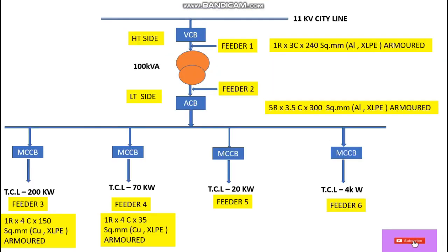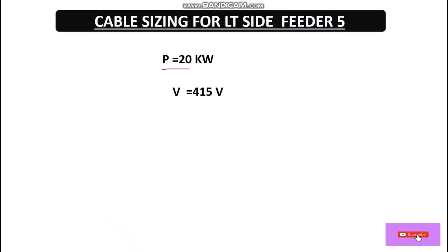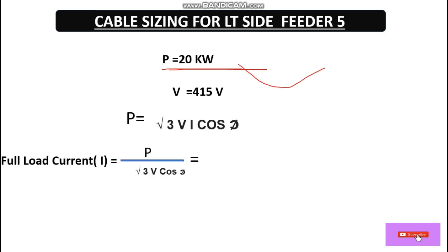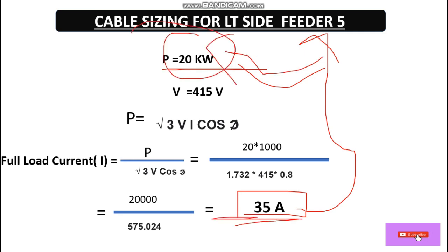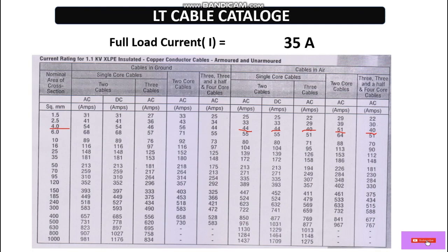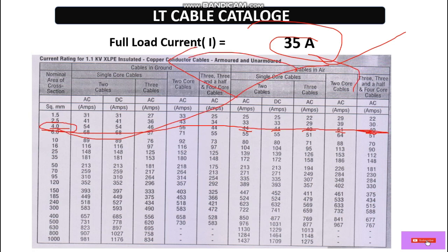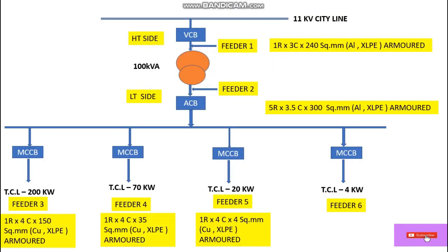Now let's move to feeder five. The total connected load for feeder five is 20 kilowatts. Calculating the current using the three-phase formula, the full load current comes out to 35 amperes. Looking into the cable catalog for 35A full load current, a 40A rating corresponds to a 4 sq mm cable. So for feeder five, one run four-core 4 sq mm copper XLPE armored cable is selected.